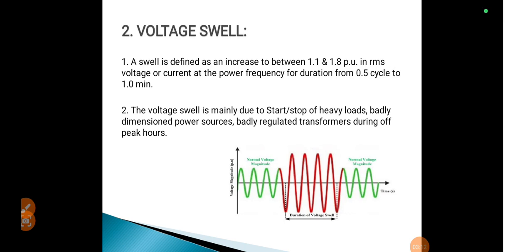The next power quality issue is voltage swell. Voltage swell means a momentary increase in voltage at the power frequency, outside the normal tolerance, for a duration of more than one cycle and typically less than a few seconds. Voltage swell occurs due to the start or stop of heavy loads, badly regulated transformers, or during off-peak hours. The effects of voltage swell are data loss, flickering of lighting and screens, and stoppage or damage of sensitive equipment.